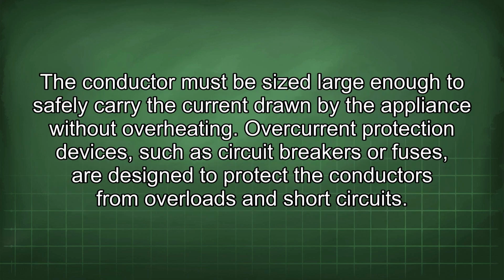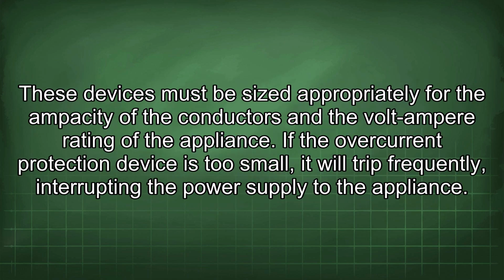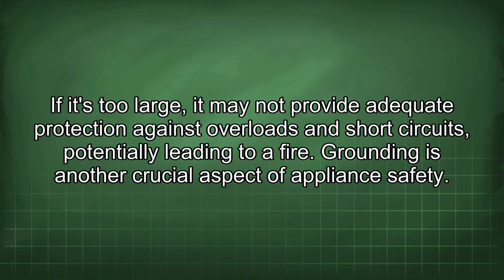The conductor must be sized large enough to safely carry the current drawn by the appliance without overheating. Overcurrent protection devices, such as circuit breakers or fuses, are designed to protect the conductors from overloads and short circuits. These devices must be sized appropriately for the ampacity of the conductors and the volt-ampere rating of the appliance. If the overcurrent protection device is too small, it will trip frequently, interrupting the power supply to the appliance. If it's too large, it may not provide adequate protection against overloads and short circuits, potentially leading to a fire.